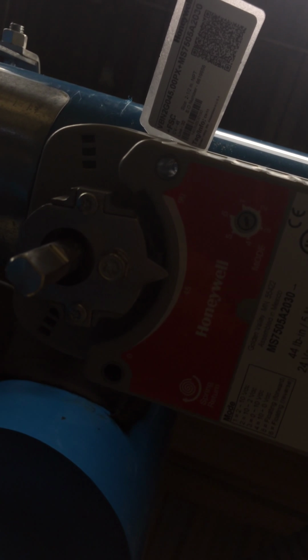So the valve seems like it is going to 0 from the 90-degree position of it being closed, and I'm going to watch that stem and see if that stem goes, like I like to say, east and west, which shows valve closure. I got my eyes on the stem. I'm thinking that the stem may be the problem, but we're going to see, because I also looked at the discharge air temp after about 5 minutes once it appeared to be closed, and as you can see, it's moving to let's say 0%.